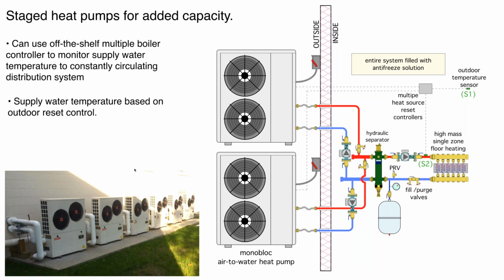But going back to a single phase situation where, again, in rural areas, you may not have 3-phase power available to these facilities, you can do staged heat pumps just like we do staged boilers. So the schematic shows 2 heat pumps, independently controlled, each having its own circulator with a check valve. And again, we're just dumping into the left side headers of the SEP4 hydraulic separator. And we maintain constant circulation in our high mass slab over on the other side. We're using off the shelf multiple boiler controls, but multiple heat source controls. The controller really doesn't care if it's a boiler or a heat pump. It's a contact closure as far as the output goes.